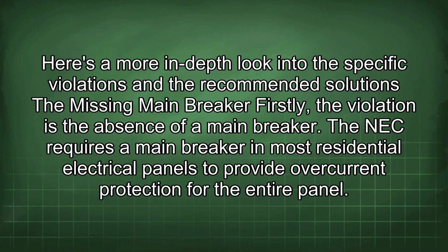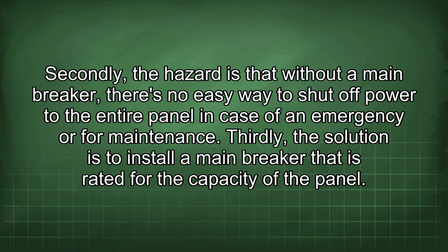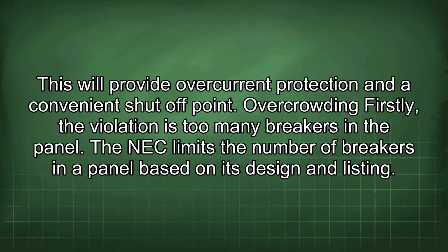Here's a more in-depth look into the specific violations and the recommended solutions. The missing main breaker. Firstly, the violation is the absence of a main breaker. The NEC requires a main breaker in most residential electrical panels to provide overcurrent protection for the entire panel. Secondly, the hazard is that without a main breaker, there's no easy way to shut off power to the entire panel in case of an emergency or for maintenance. Thirdly, the solution is to install a main breaker that is rated for the capacity of the panel. This will provide overcurrent protection and a convenient shut-off point.